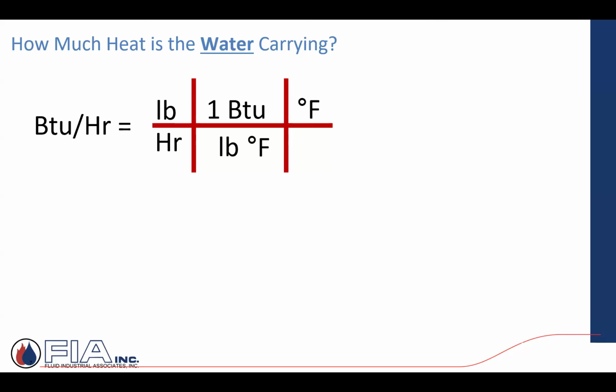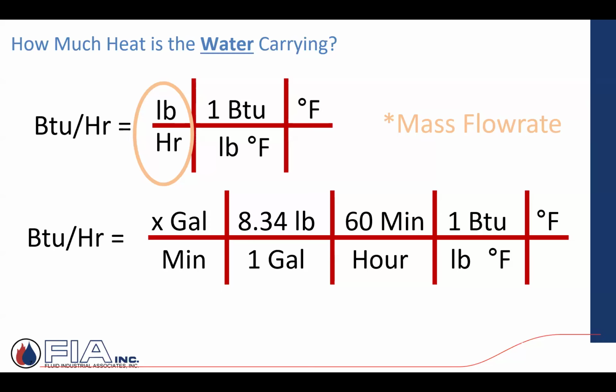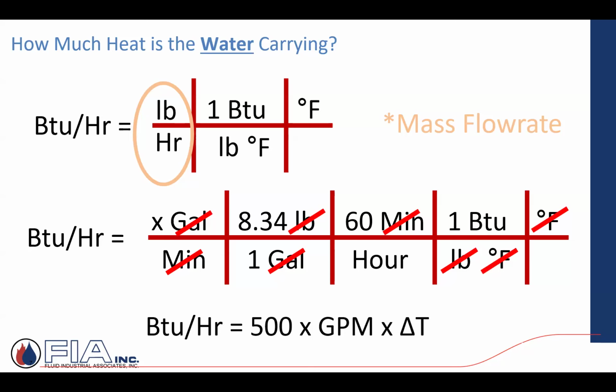So we have pounds per hour times 1 BTU per pound per degree Fahrenheit. What we need to do is we have this mass of water, this weight of water. We're going to define it so that we can establish a flow rate of gallons per minute. So when you start plugging in this whole formula and numbers start to cancel each other out, at the end you end up with a standard formula that's used in the hydronics industry. And it's saying 500 times gallons per minute times delta T will provide the BTUs per hour that we're chasing, that we want, that we need.